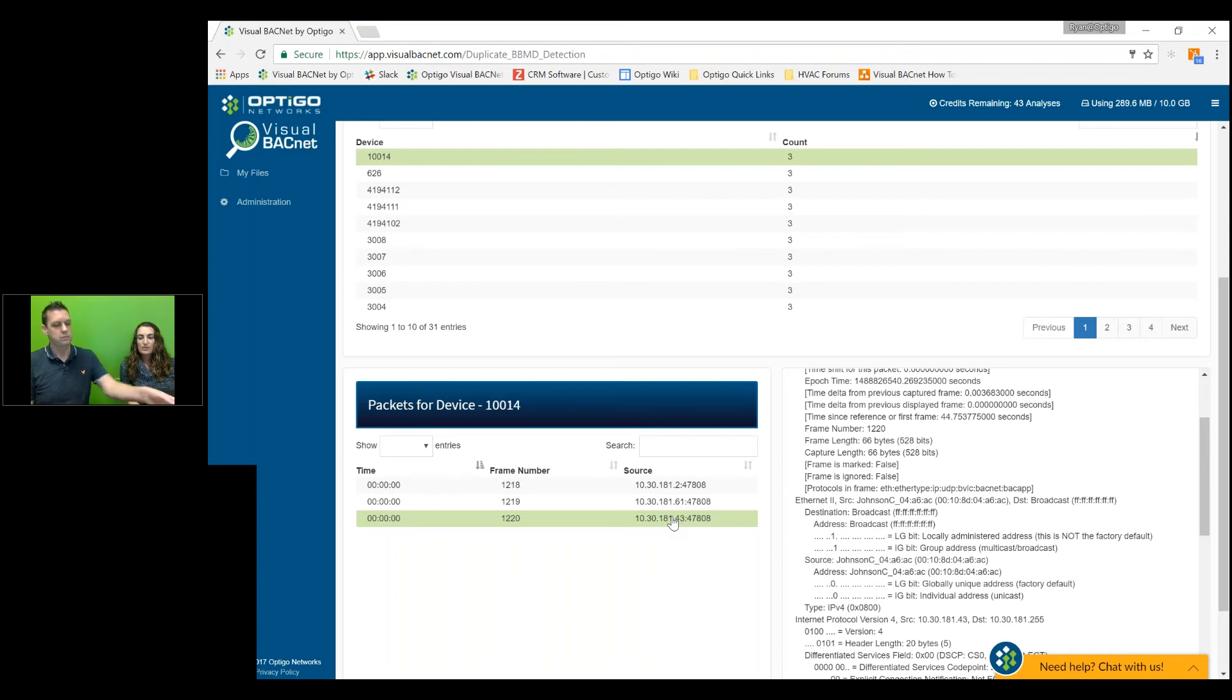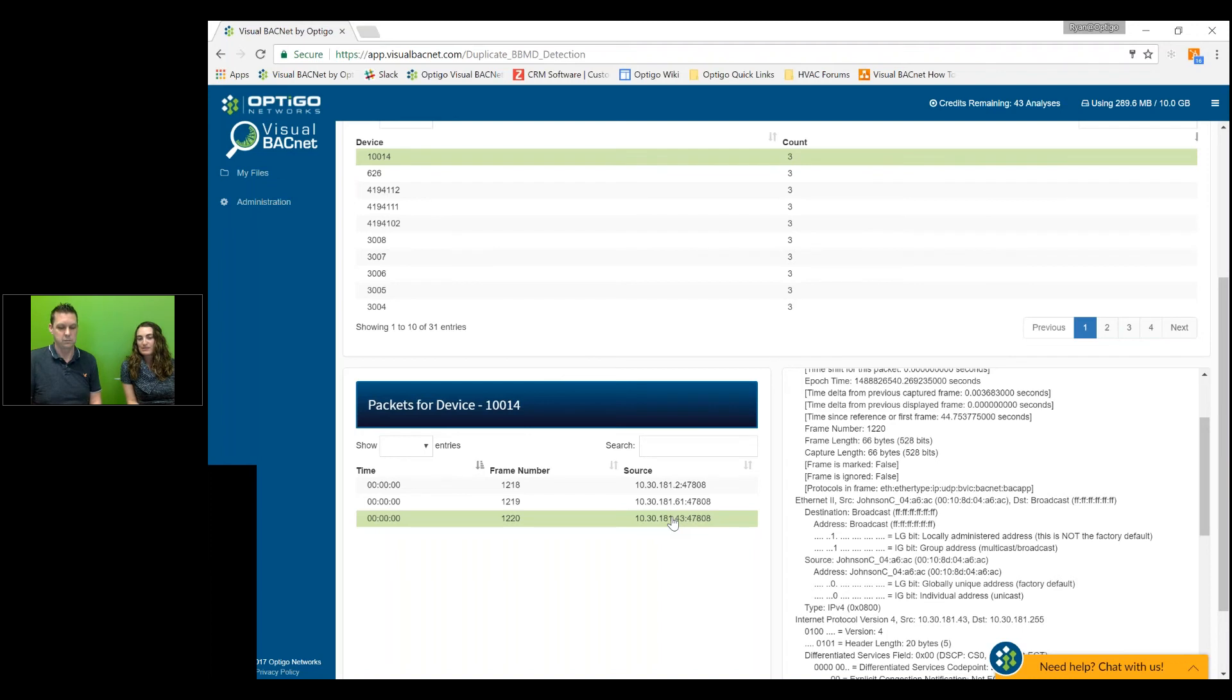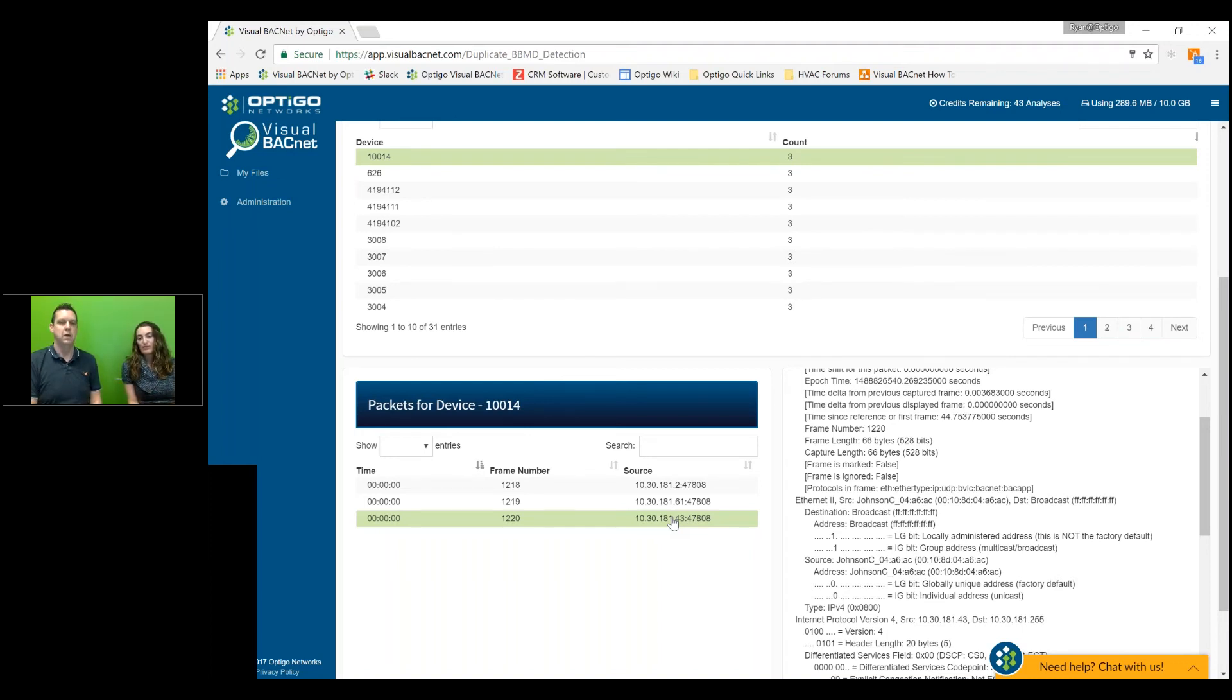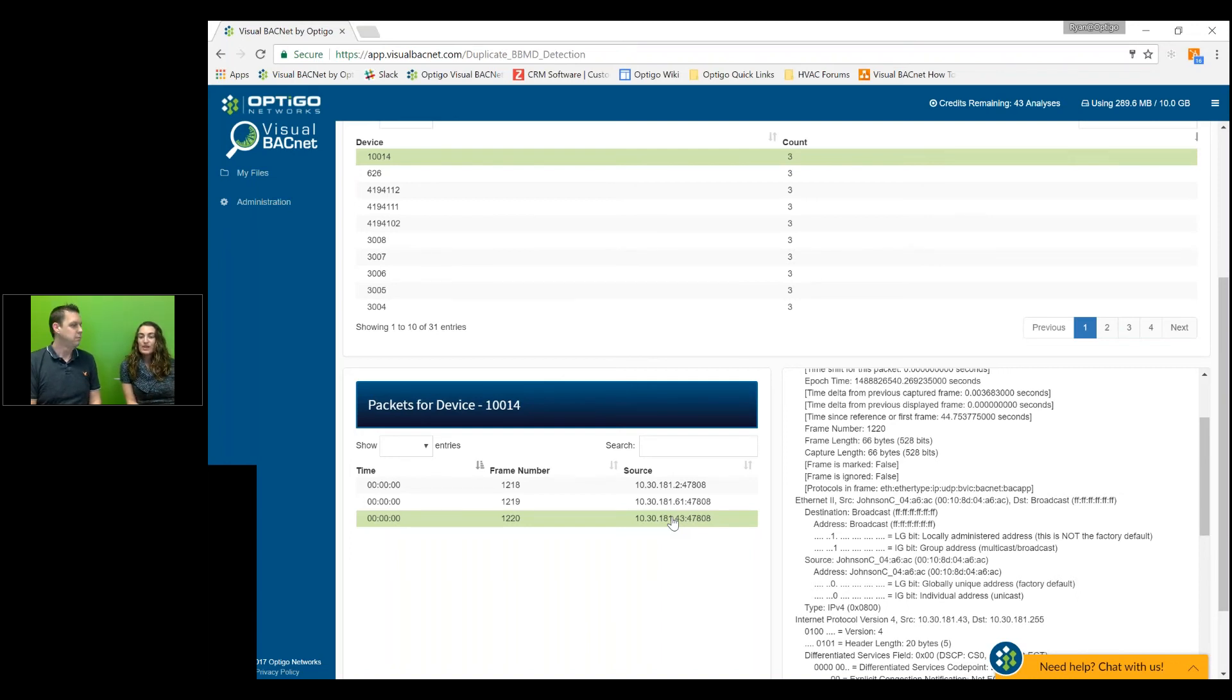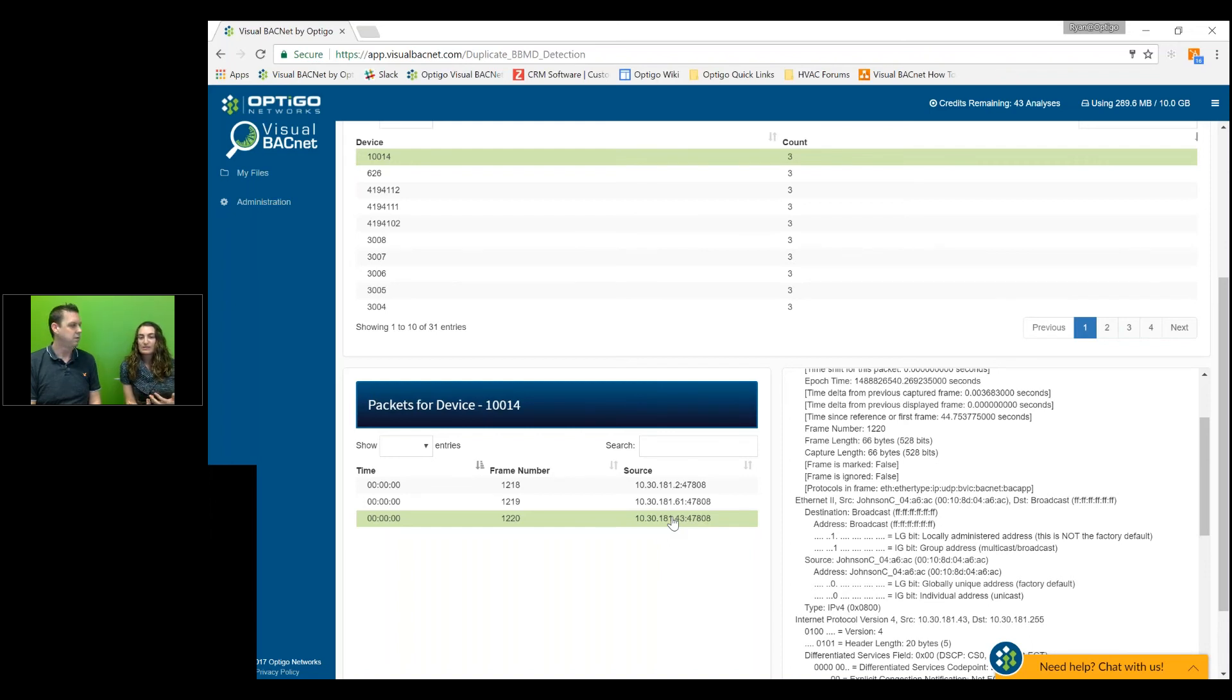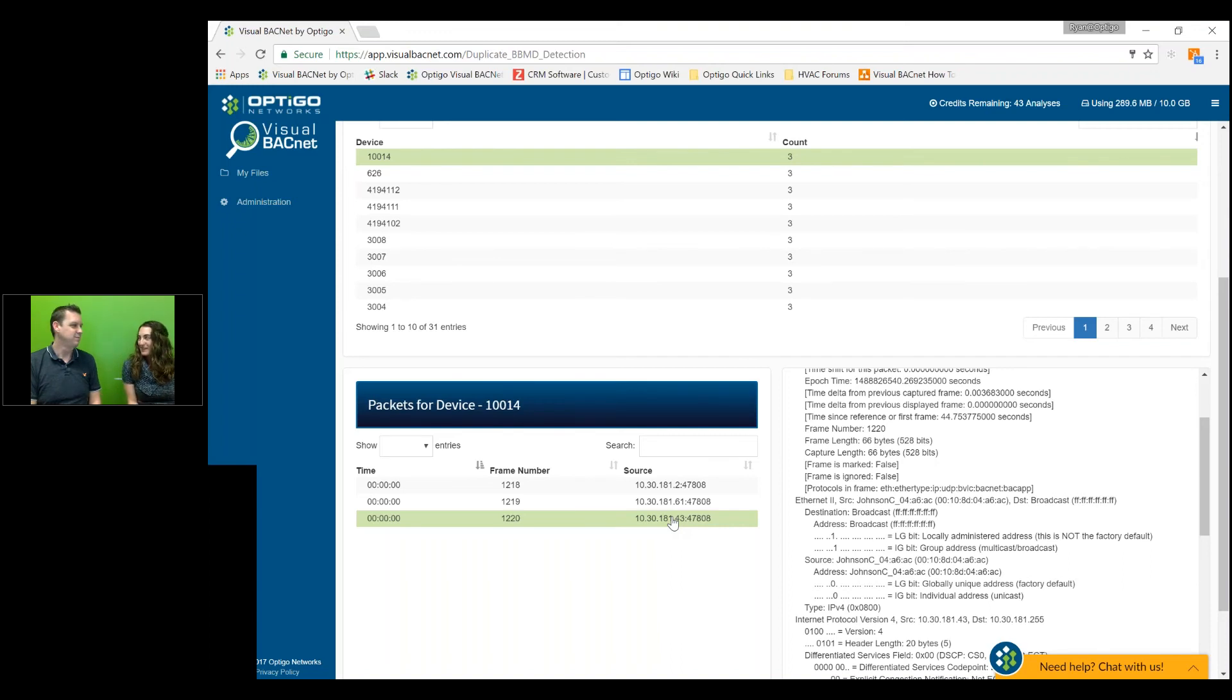And so this was exactly as expected. Three different vendors putting BBMDs and having that same device, the device 10014 information, being rebroadcasted by three different devices. So any other tips for solving that and what the vendor, you escalate this. The person that's escalated to is on this call. What are they going to do?